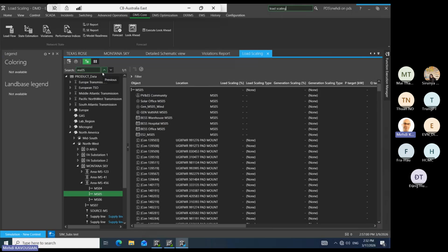But you can say, all right, what if at the time that I want to do that switching, the load is more, like 20% more, because you want to have some reserve, right? You want to be on the safe side. If you don't do anything, it assumes from load profiles. The load profile you already defined for each load is kind of an average for that specific time, right?